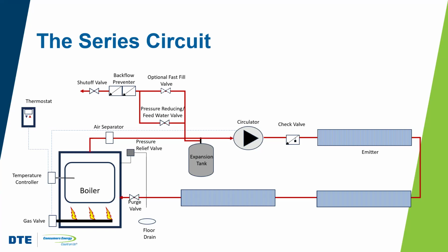So the other downside to this system is that you can see it, since water's flowing through all of the emitters, you can't turn anything off, right? There's no zoning, there's no independent control of any single emitter, right? You can't even regulate a single emitter because that's going to impact everything else downstream, right? So everything is on, everything is open, right, all of the time.